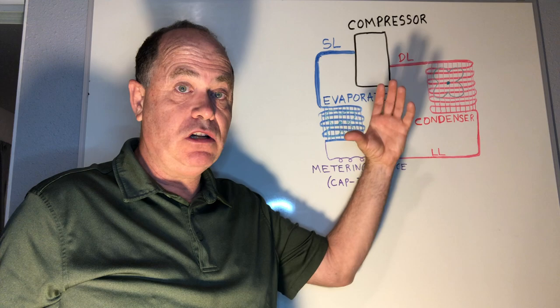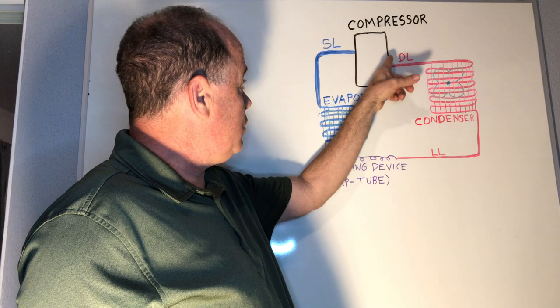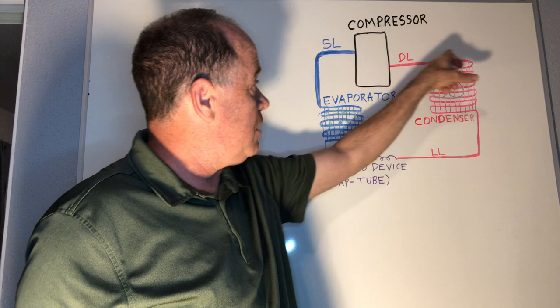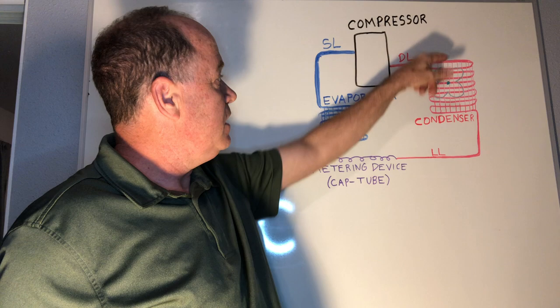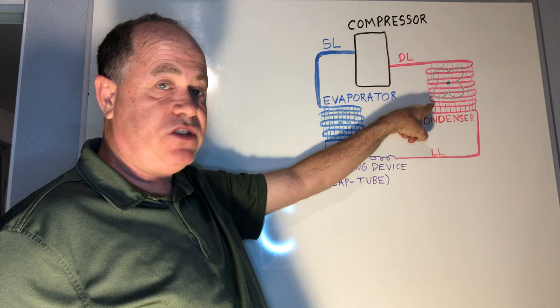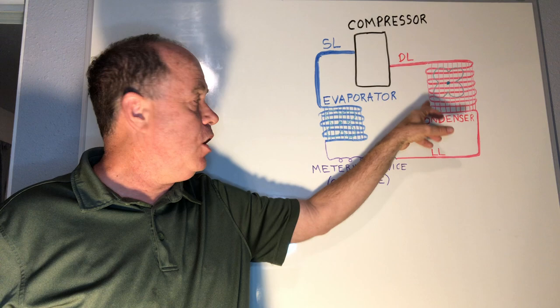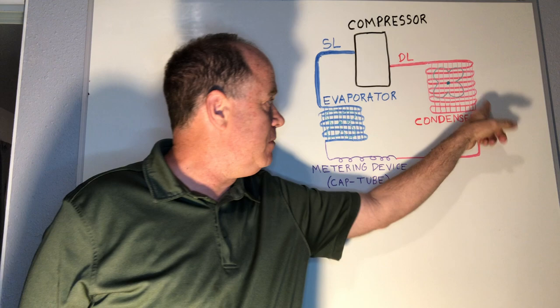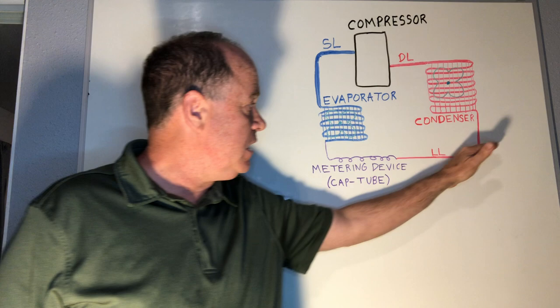The compressor sucks the refrigerant from the suction line and discharges it out the discharge line — hot, highly superheated vapor. As it travels down the discharge line it starts cooling even before the condenser. Traveling through the condenser it condenses — going from 100% vapor to mixed states to 100% liquid at perhaps 100°F. Then additional heat is removed, and if you measure 80°F on the liquid line with a condensing temperature of 100°F, you have 20 degrees of sub-cooling. Then the cycle repeats.